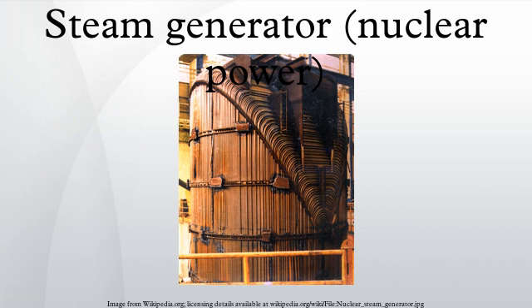In the Three Mile Island disaster, a main feedwater pump shut down, although the cause is not known. Without that pump, the steam generator wasn't able to remove heat from the reactor, so pressure in the reactor began to rise. The system automatically began to dump water from the reactor to reduce pressure, but the relief valve got stuck open when the automation told it to close. The control room indicated that the valve was closed. The staff, therefore, had no idea that they were dumping radioactive water out of one of their reactors. With the water being pumped out, there wasn't enough emergency cooling water and the staff was unaware that they were losing more by the minute.